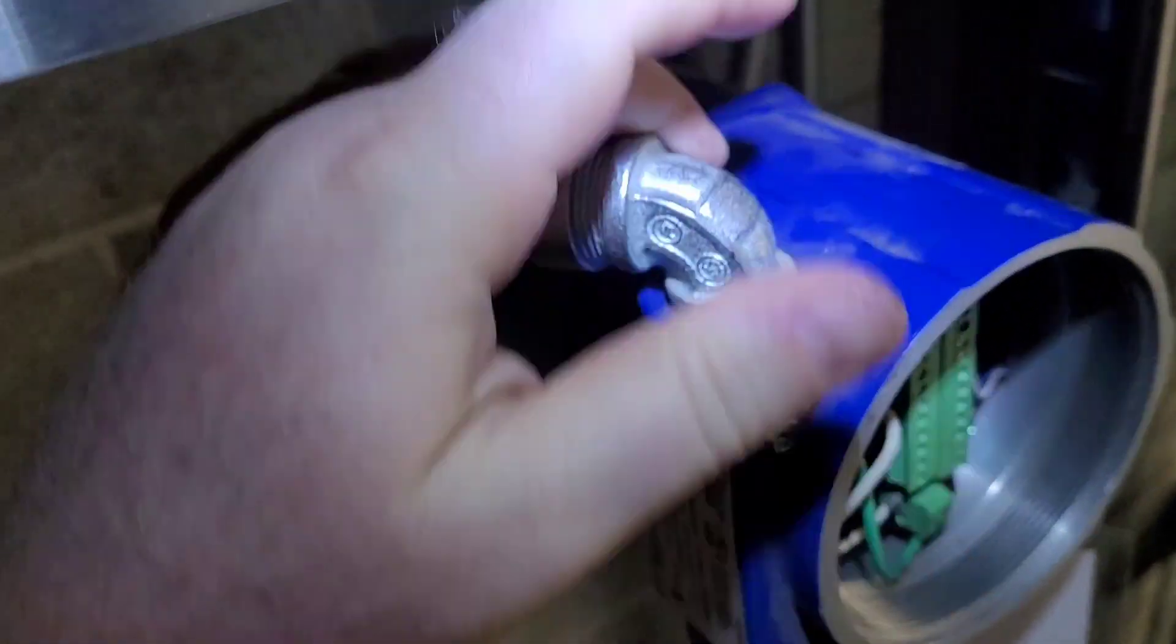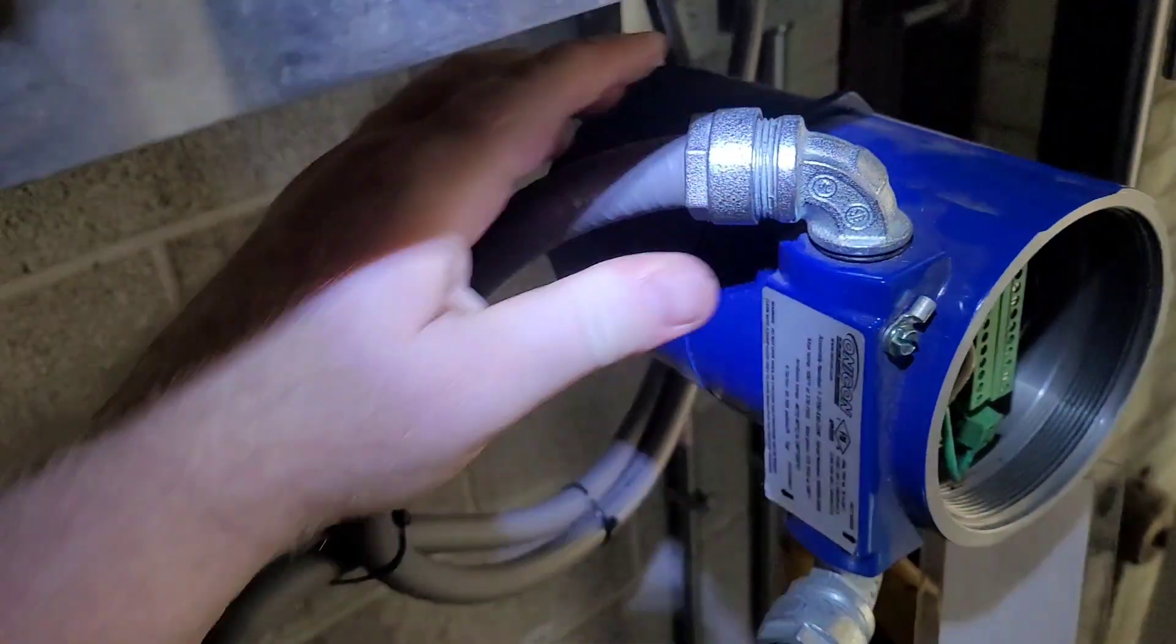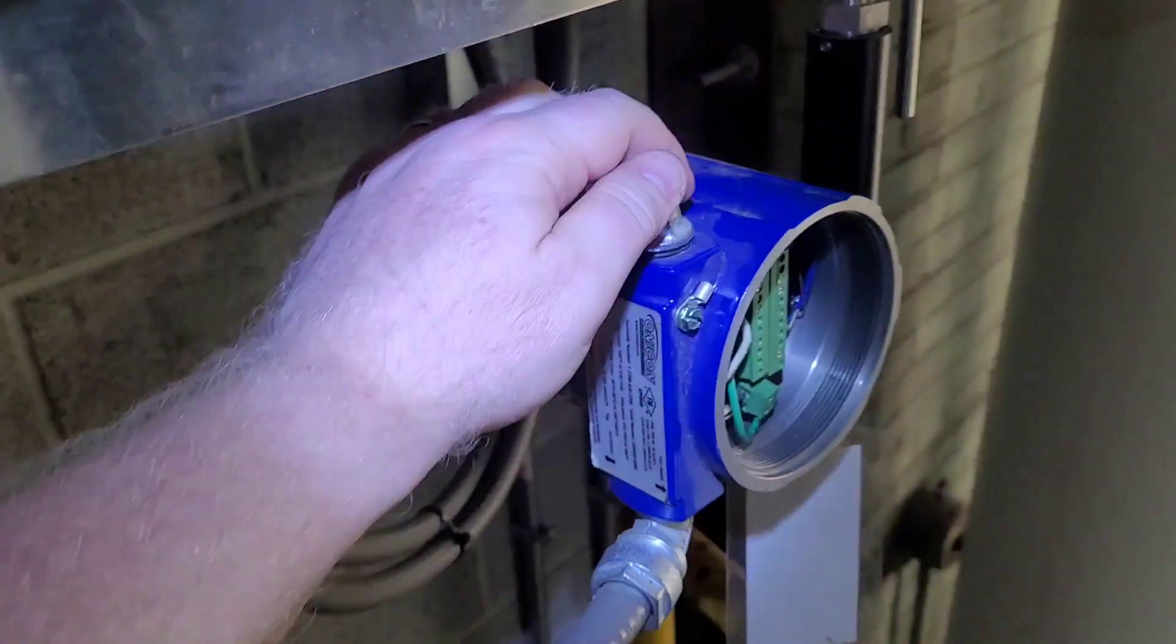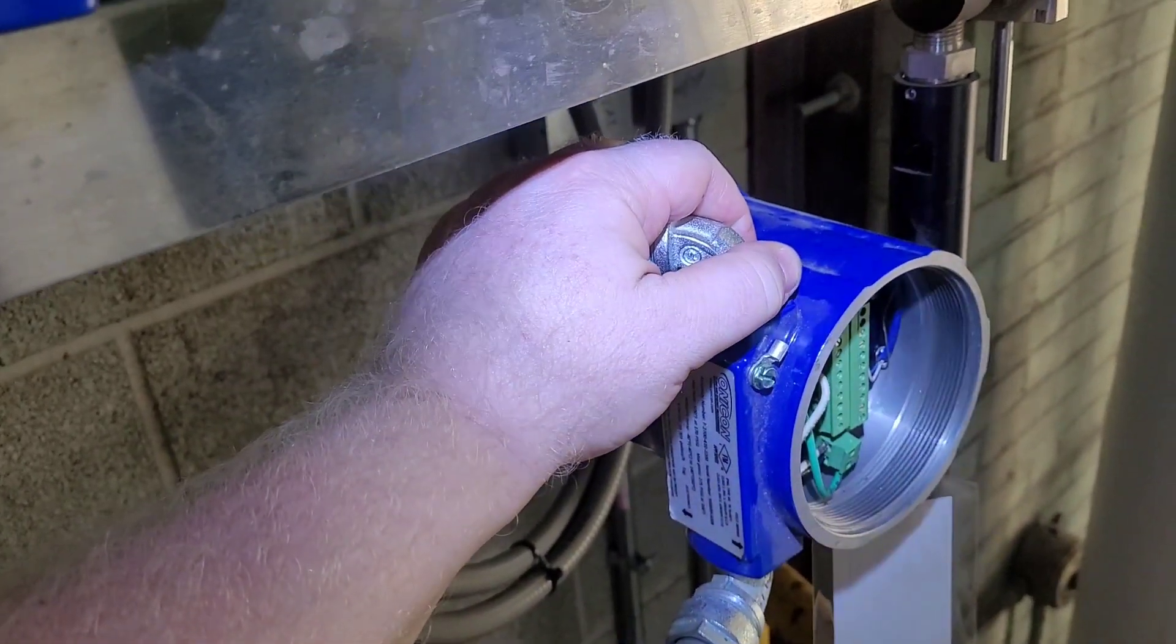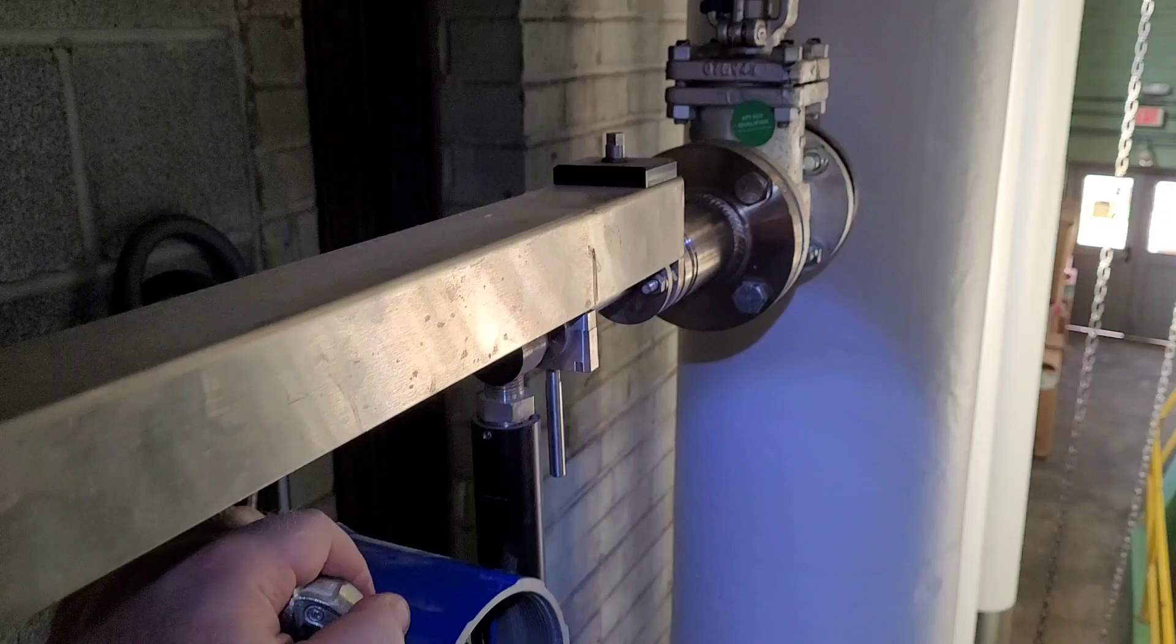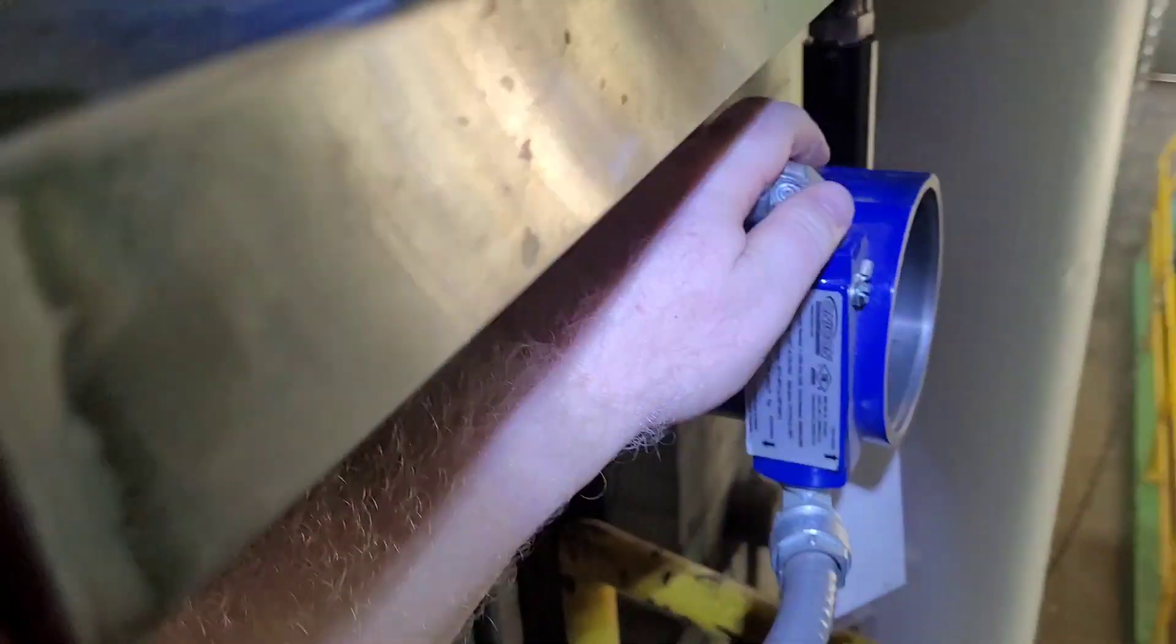The calibration on these is something that you would have to work very closely with your supplier to make sure that you get everything correct. Because the amount of flow that goes through a particular line will play into the accuracy of these steam meters.